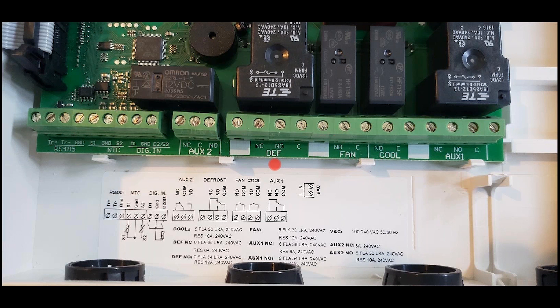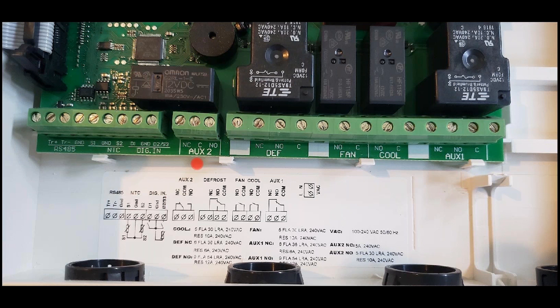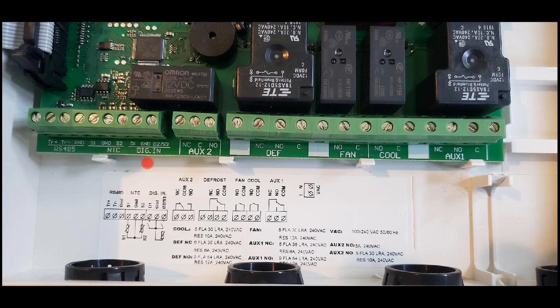Next we have a second set of auxiliary contacts, and these contacts once again can be used to power whatever loads you choose, whether it's a door left open alarm, a temperature alarm, lighting, you name it. These can be powered by these contacts. You have a digital signal input which could be something like a low pressure control, it could be a high temperature cutout, whatever you want it to be. Something can be put in there that would be a digital on-off input.